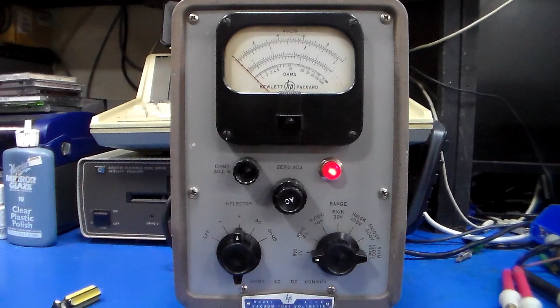The only thing was that the zero adjustment range had obviously been slightly increased with an extra resistor in parallel with a 6K8 resistor that's in that part of the circuit to bring it down to about 5K4, so it'll give a slightly bigger adjustment range on the zero, but that doesn't seem to really be an issue here. I went then next to start verifying the calibration of the DC. You first have to set the DC gain of the system up before any of the other modes like AC or ohms can be calibrated with any degree of confidence.